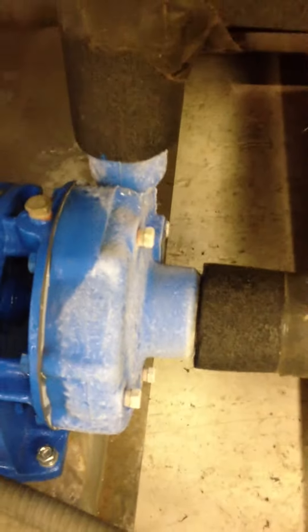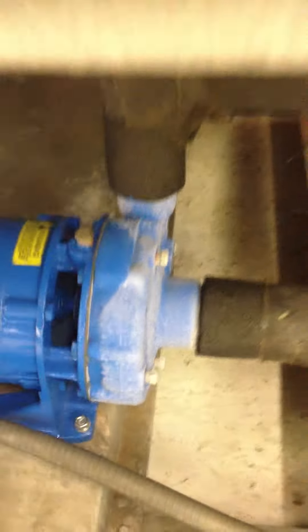That's a rebuilt pump. Notice a little bit of frost on there, but because we were running it below 20°F, which is kind of good. That's the compressor. This here is a low pressure cutoff switch we just installed as a safety.